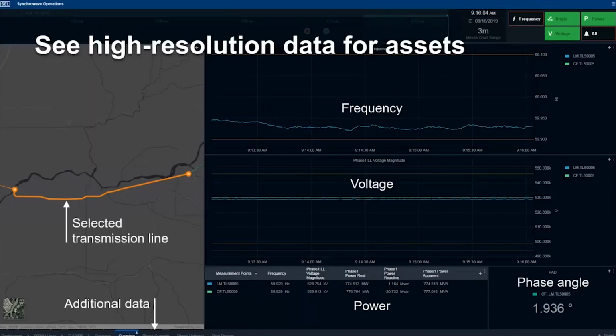Hi, Hardesh. Yeah, there are a few questions. The first question we have is, what is the required load for the FT50 to start transmitting? For the FT50, it's 5 amps. So it needs up to 5 amps of load current to develop a link status with the FT50. But if the load current is less than 5 amps, it's not that it won't send fault information. It's still going to send the fault information, but it's going to take a little longer for the FT50 to transmit that information. But again, the short answer to your question is 5 amps of load current.